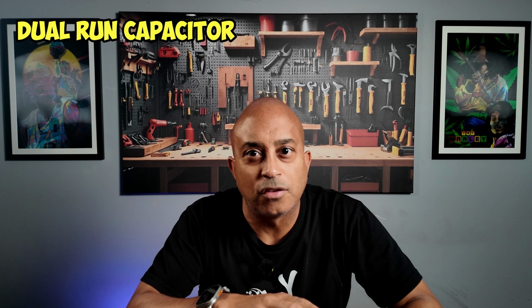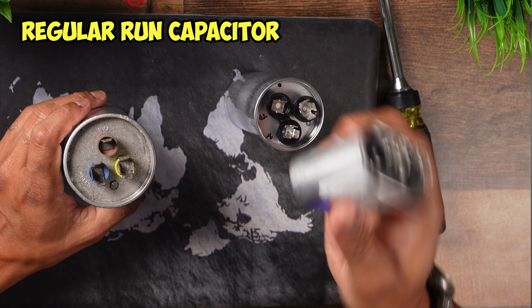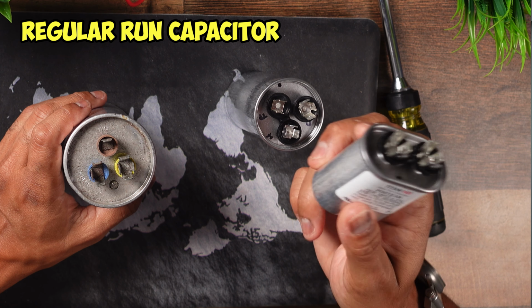This capacitor with 3 terminals is called a dual run capacitor. Why? Because it controls both the fan and the compressor in your outdoor unit. This one just has 2 terminals and it's a regular capacitor, and it will control one device, either your fan or your compressor.